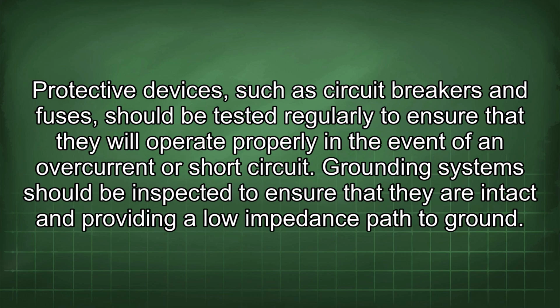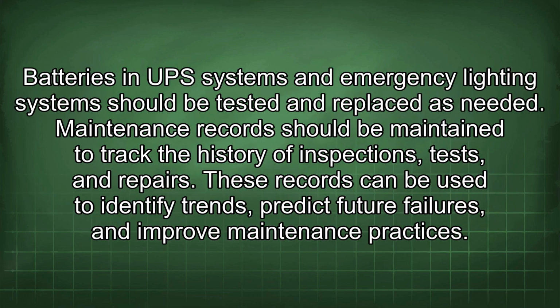Protective devices, such as circuit breakers and fuses, should be tested regularly to ensure that they will operate properly in the event of an overcurrent or short circuit. Grounding systems should be inspected to ensure that they are intact and providing a low impedance path to ground. Batteries in UPS systems and emergency lighting systems should be tested and replaced as needed. Maintenance records should be maintained to track the history of inspections, tests, and repairs. These records can be used to identify trends, predict future failures, and improve maintenance practices.